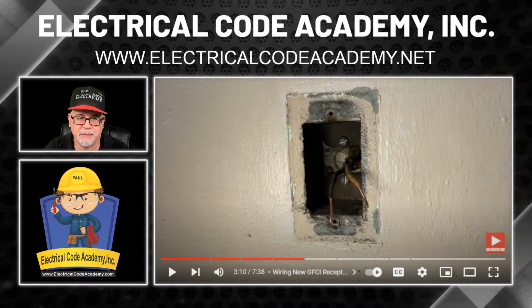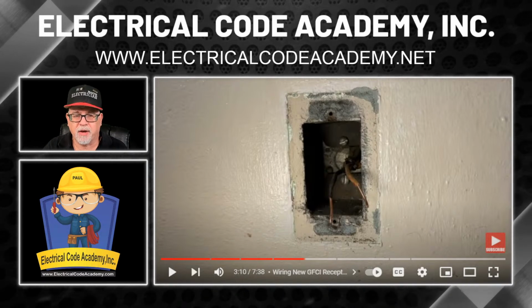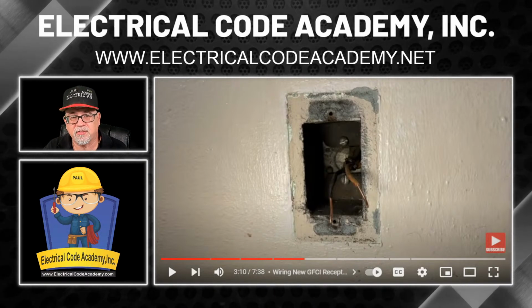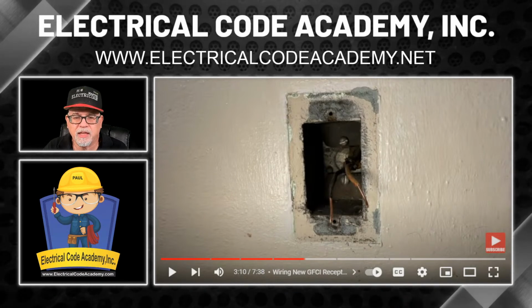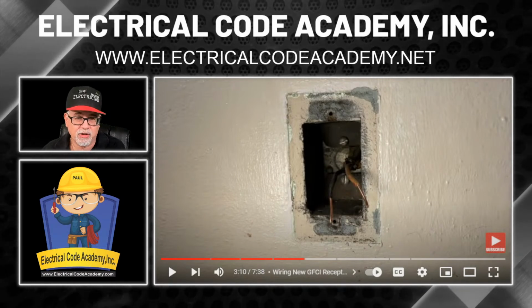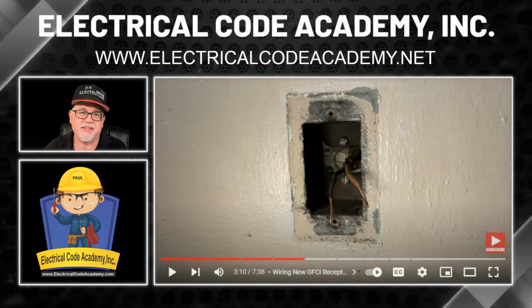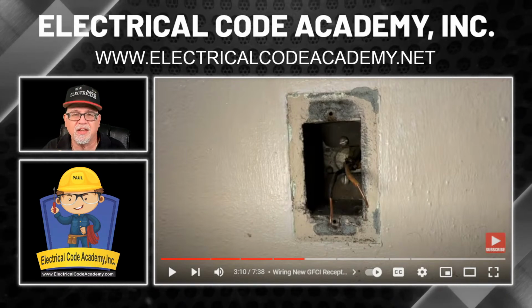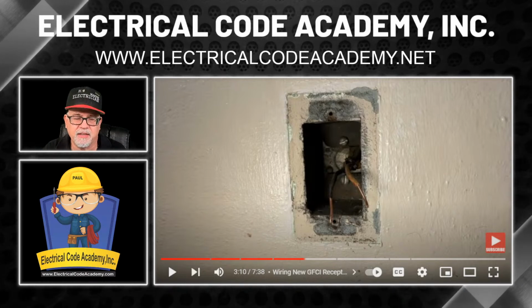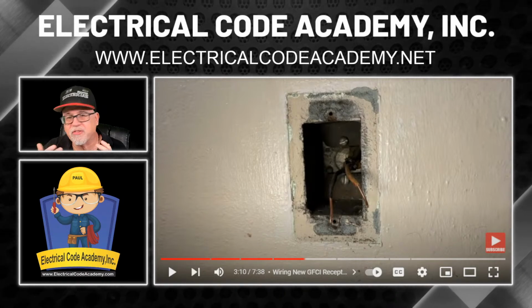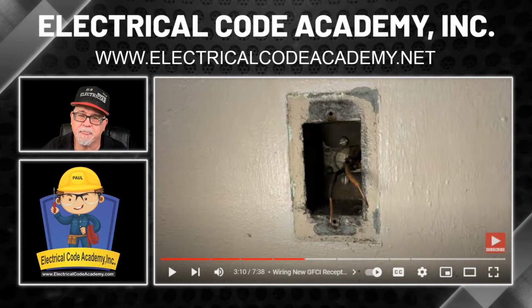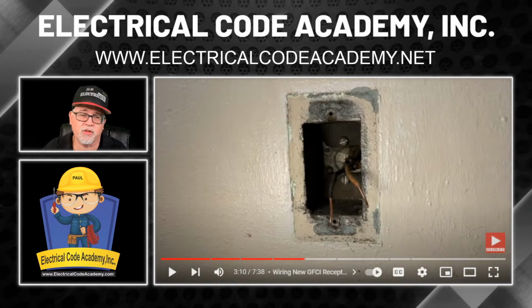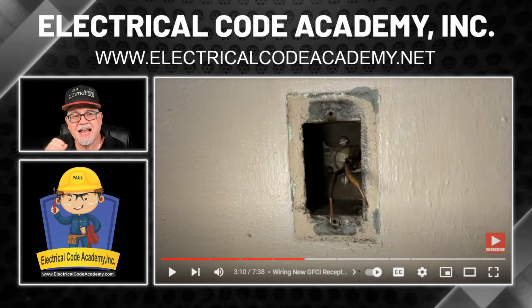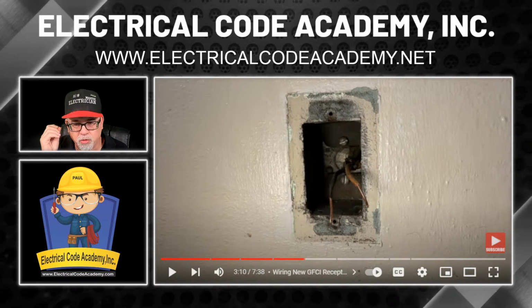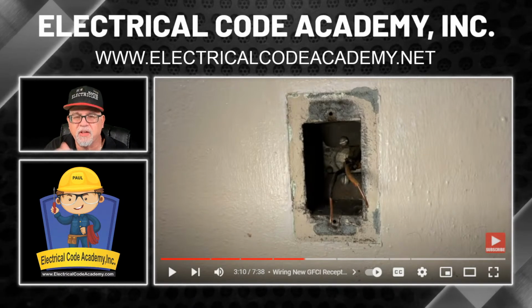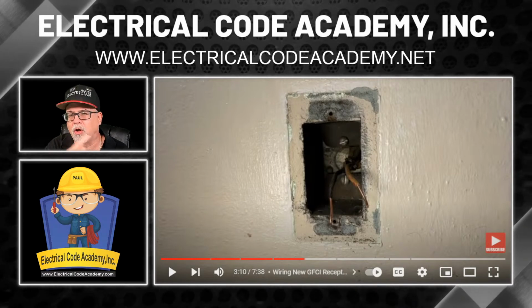That's the traditional MC. Now, they do make smart products, or like we say, advanced, enhanced type of MC, where the armor can be used as an equipment ground. And that typically goes up to 6 gauge and doesn't get any larger than that. So it's not the large feeder type MC that can get that smart ground, or Southwire has one called MCAP. Encore Wires is called Smart Ground. That has a conductor that runs, it's aluminum, it runs through with the insulated conductors, and it makes an intimate contact with all of the armor.